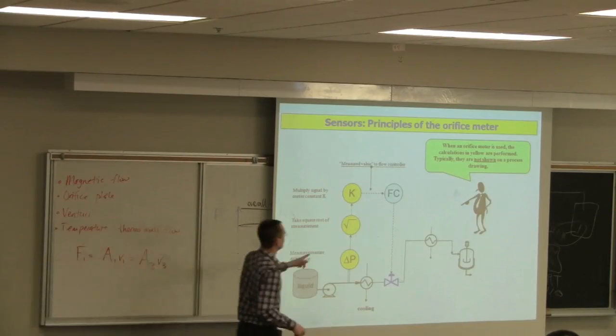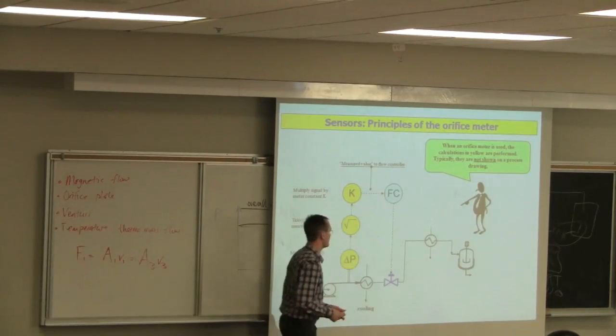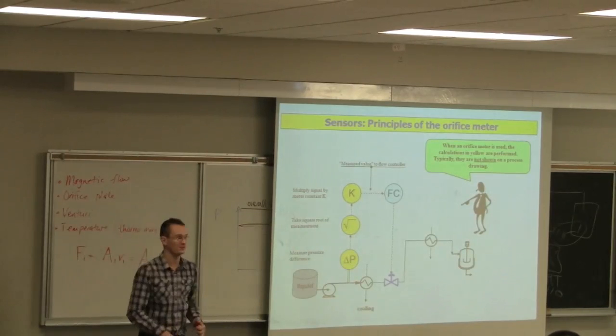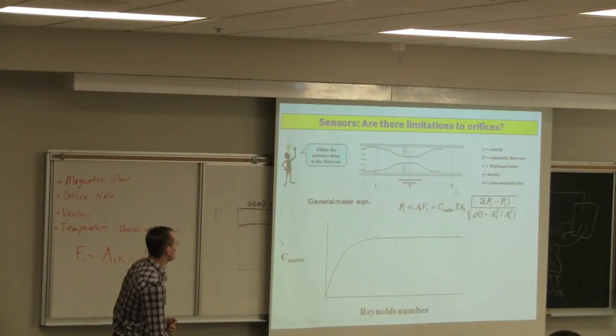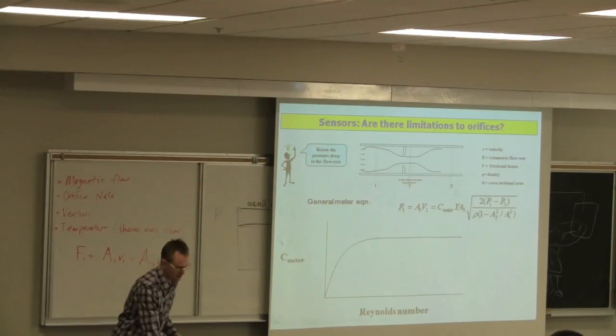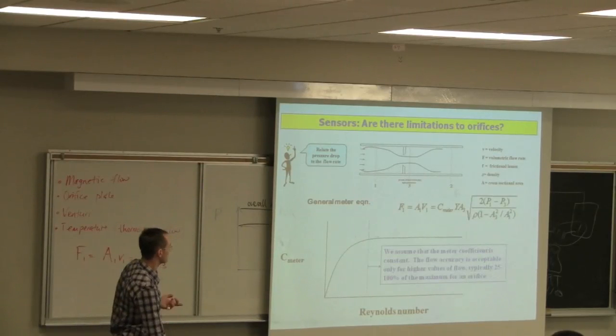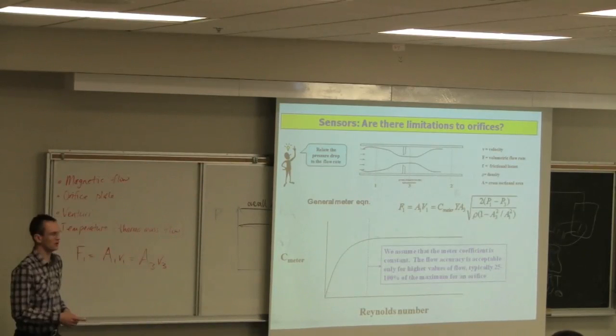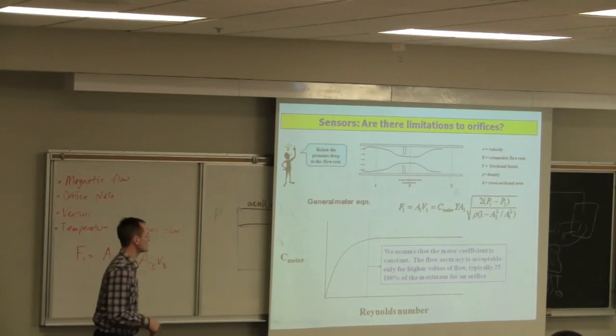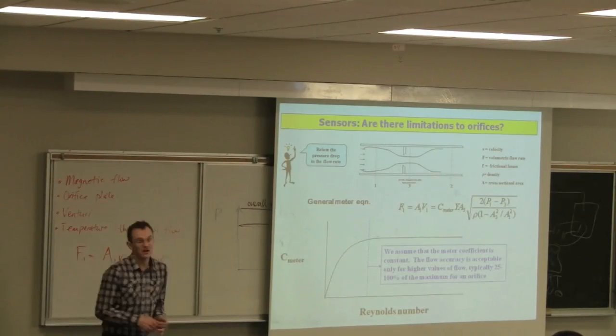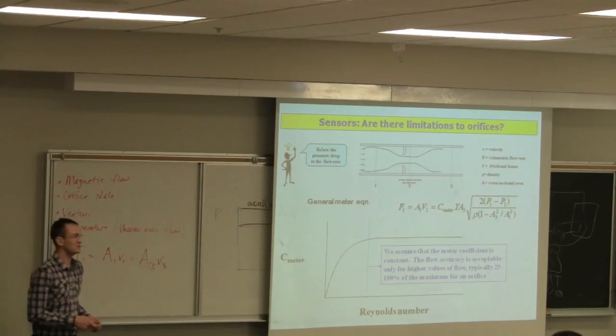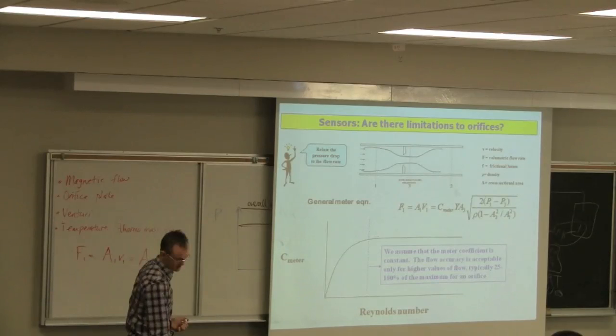One other thing to be aware of is that k is a function of the Reynolds number. We typically assume that's constant as well - we're operating at a high enough velocity that our Reynolds number is not going to affect that constant k. That impacts the accuracy of the flow meter at really low flows. We would expect a higher error at low flow.